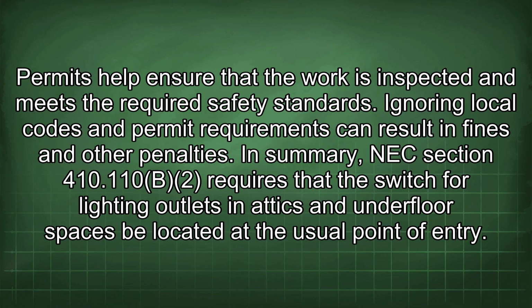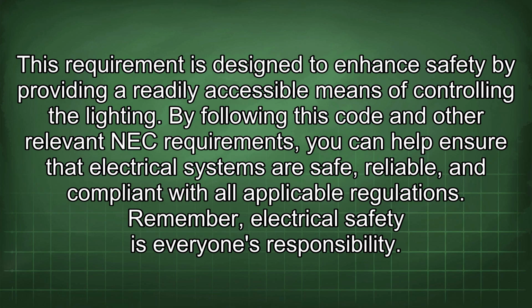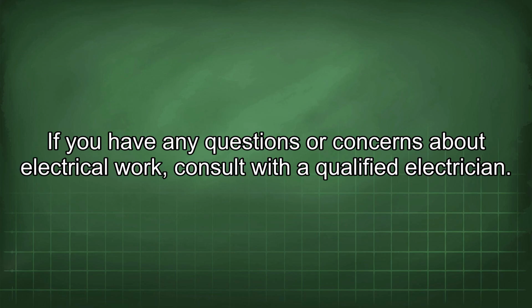In summary, NEC Section 410.110b2 requires that the switch for lighting outlets in attics and underfloor spaces be located at the usual point of entry. This requirement is designed to enhance safety by providing a readily accessible means of controlling the lighting. By following this code and other relevant NEC requirements, you can help ensure that electrical systems are safe, reliable, and compliant with all applicable regulations. Remember, electrical safety is everyone's responsibility. If you have any questions or concerns about electrical work, consult with a qualified electrician.